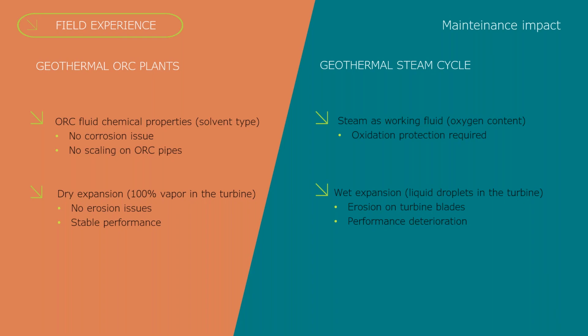And for this reason, steam cycles generally require a periodic maintenance, consisting in the opening of the turbine and refurbishment of the turbine blades. That is essential to keep the performances. On the other side, in the ORC plants, the organic fluid expands fully in the vapor region, so there is no matter for the blades at all, which has the key consequence of making the maintenance of these plants much easier. There is no performance degradation, no invasive maintenance on the turbine.